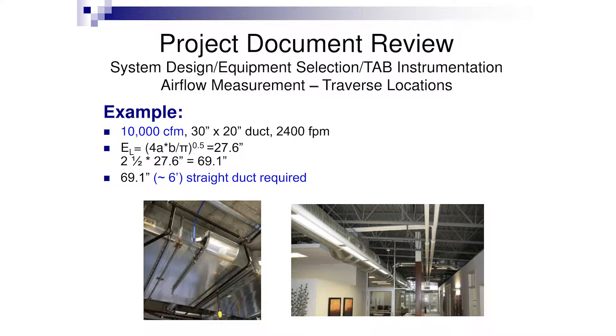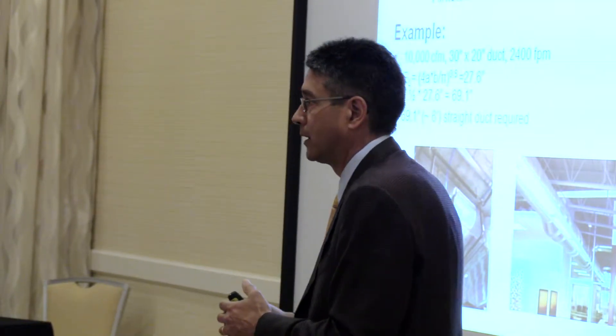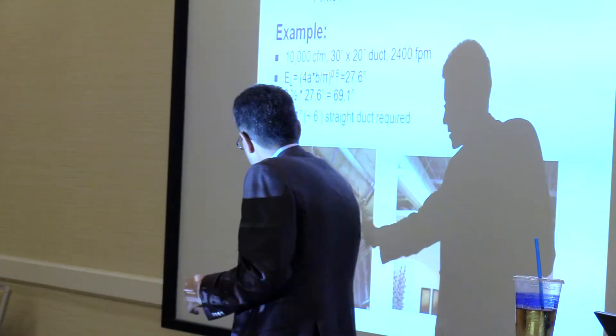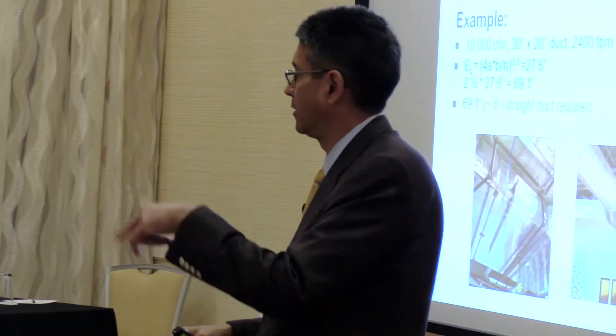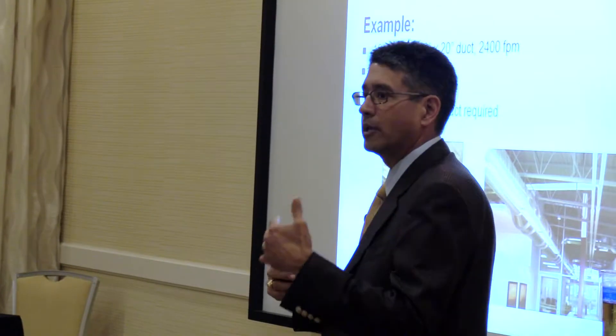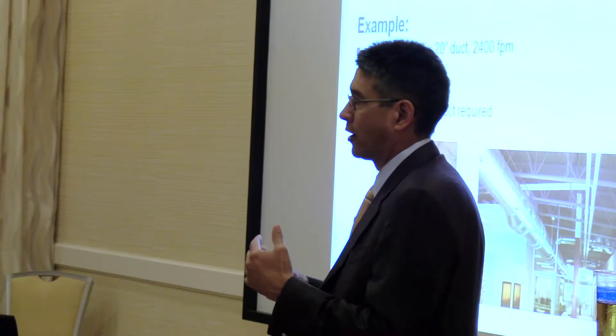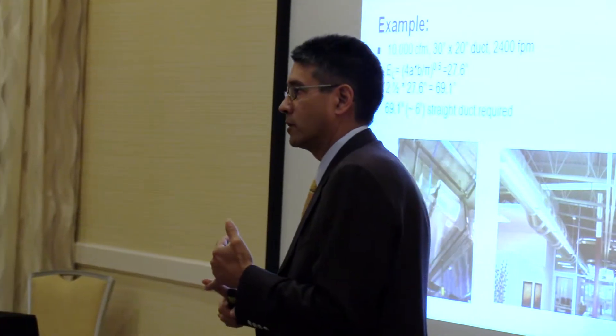As an example, a 30-inch by 20-inch duct for 10,000 CFM needs approximately six feet of duct for an accurate traverse location — an ideal traverse plane. How often do you get six feet of duct on a 30 by 20? Very seldom. You see a lot of things done in the field, but if that airflow measurement needs to be accurate, we're going to go with a duct traverse. When looking at air handlers, rooftop units, big supply units, we'd definitely love to get a duct traverse on those.